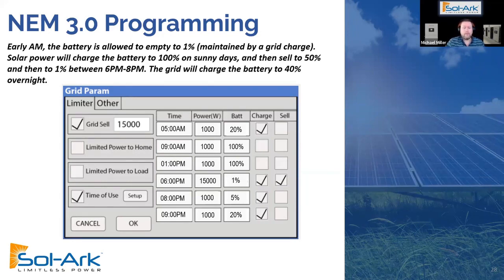So we're telling the inverter to use 1,000 watts during regular hours, and then at the 6 p.m. power hour start, we tell it to drop the battery as fast as it can—discharging 15,000 watts for 2 hours—and then bring it back up to, say, 5%.